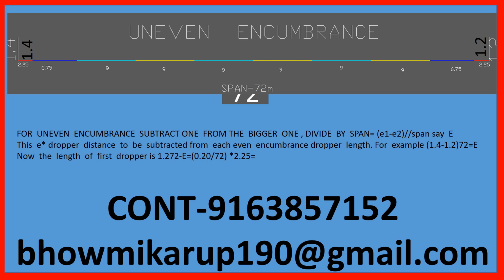Friends, here I have shown how to find out the uneven encumbrance dropper length, to adjust or subtract from the even span dropper length the value of E, that is 1.4 the first mast minus 1.2 the second mast, divided by the span in meters.